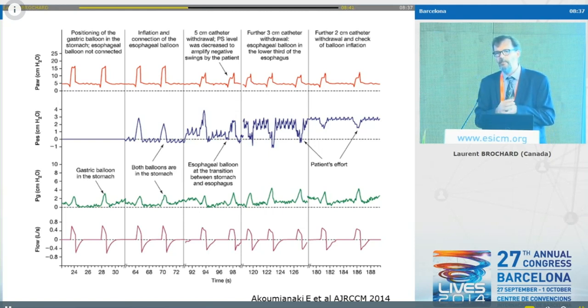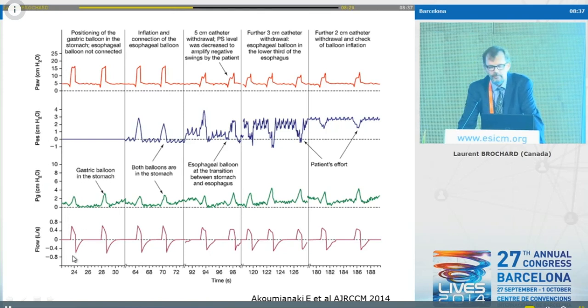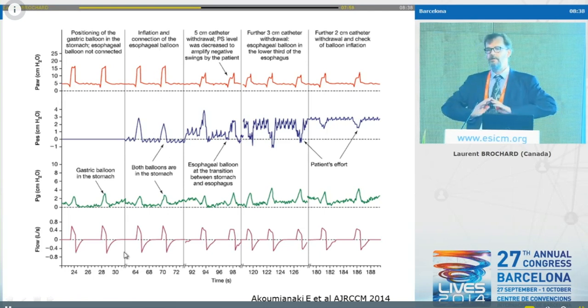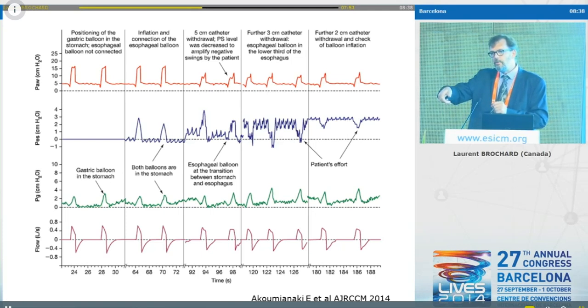And here we have described one way to do it, which is to insert the catheter as far as possible. For instance, this is a catheter with an esophageal and a gastric balloon, and you have the recordings of the airway pressure and the flow, the signals from the ventilator, and the esophageal pressure and gastric pressure. In the first recording you see positive deflections on the gastric balloon and positive deflections on the esophageal balloon, which means that the 2 balloons are below the diaphragm, because when the diaphragm is contracting at every breath during pressure support ventilation, there is a positive deflection. So you're too far.